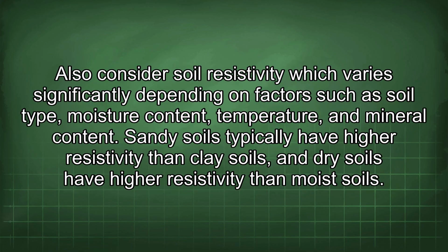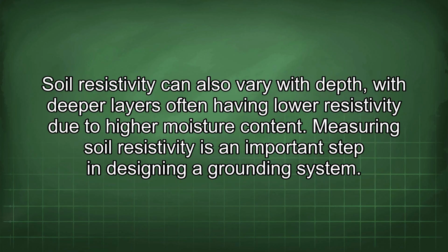crucial. Also consider soil resistivity, which varies significantly depending on factors such as soil type, moisture content, temperature, and mineral content. Sandy soils typically have higher resistivity than clay soils, and dry soils have higher resistivity than moist soils. Soil resistivity can also vary with depth, with deeper layers often having lower resistivity due to higher moisture content. Measuring soil resistivity is an important step in designing a grounding system.